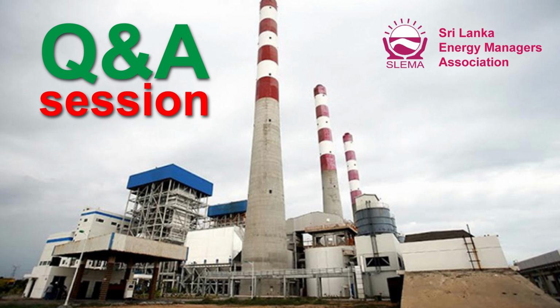The second one is what Nirmal was explaining to you. Even if you have an on-site auxiliary power source, the fact that particularly the feed pump and the cooling water pumps have tripped means getting those pumps back in operation is a complex operation. It takes time, many things to be checked, priming, etc. But it still gives a better chance of saving the power plant from going through a rupture disk situation, which will put it out for 4 days, as we saw this time.